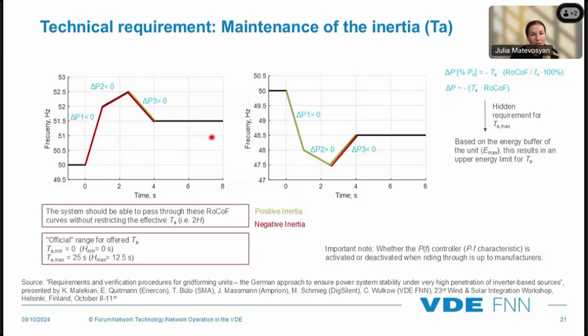And so depending on the direction in which they offer this momentary reserve, they'll be tested for provision of inertial type of response. But what's also interesting is if they offer, say, in the negative direction, so during overfrequency, they'll offer to reduce the active power output. They are also expected to respond to this negative rate of change of frequency by injecting power back. So basically, if you have provided frequency response in a negative direction, you're also expected to provide it back in the positive direction.